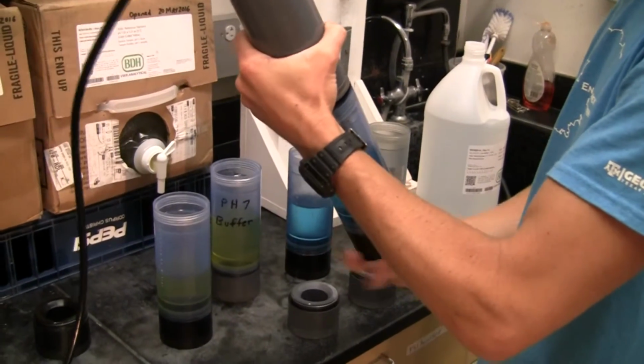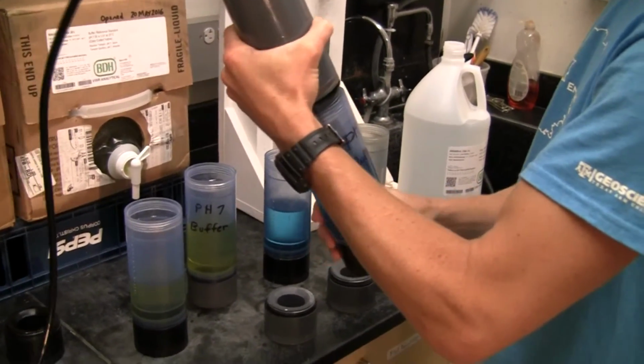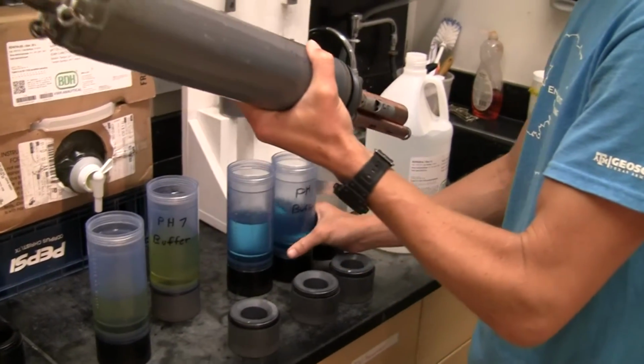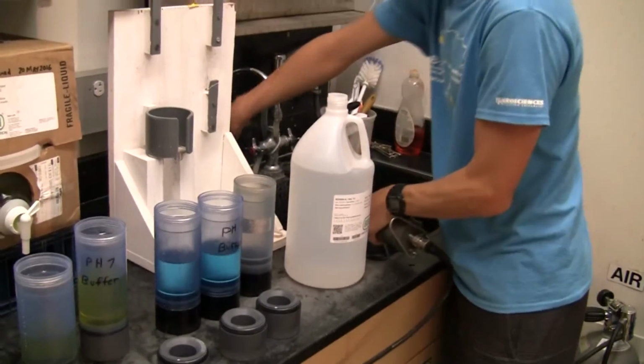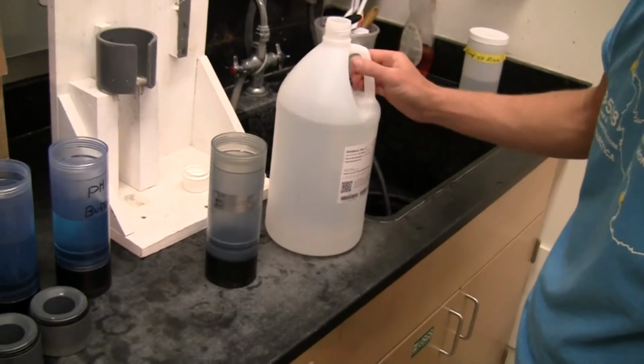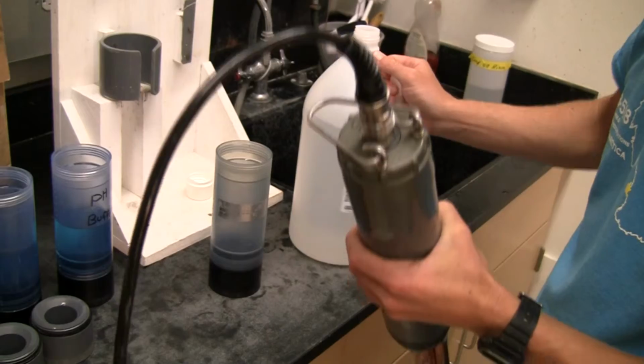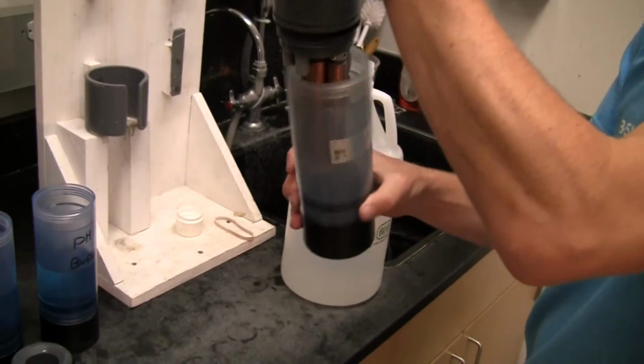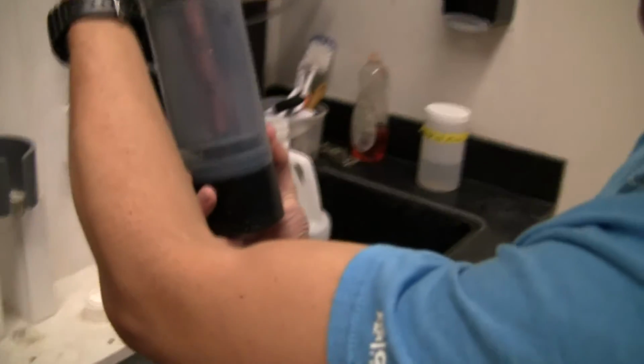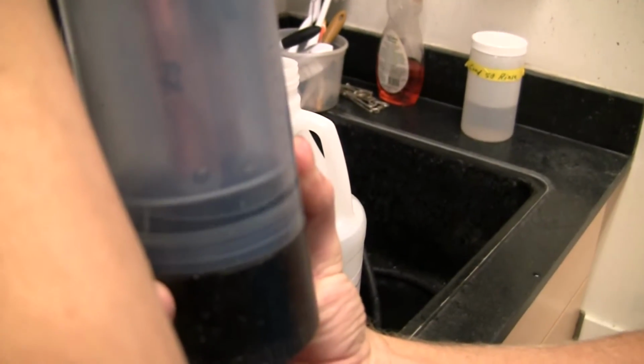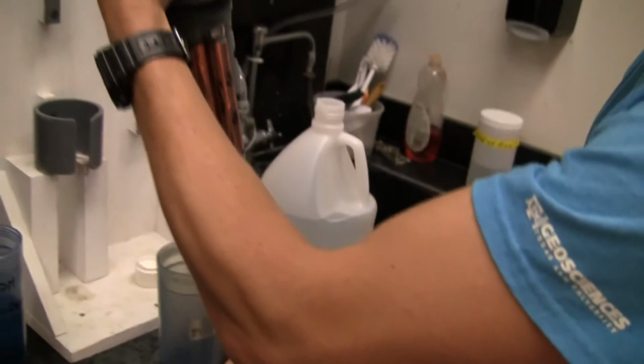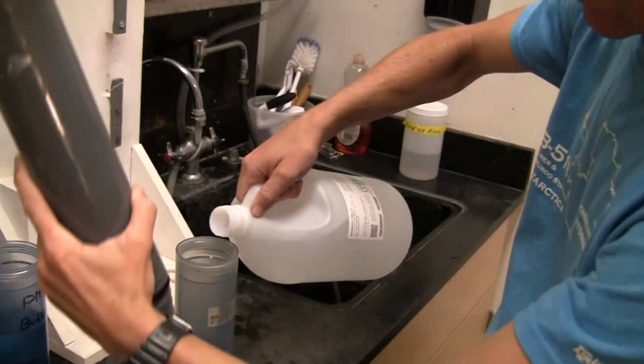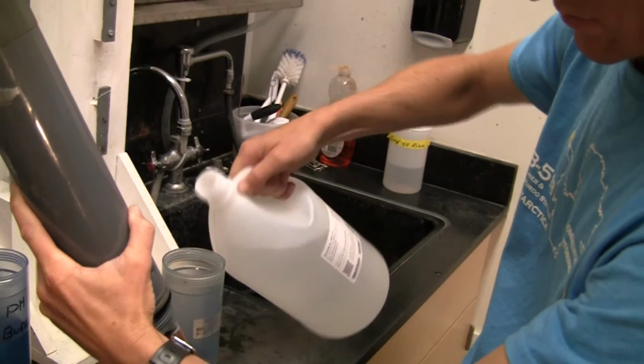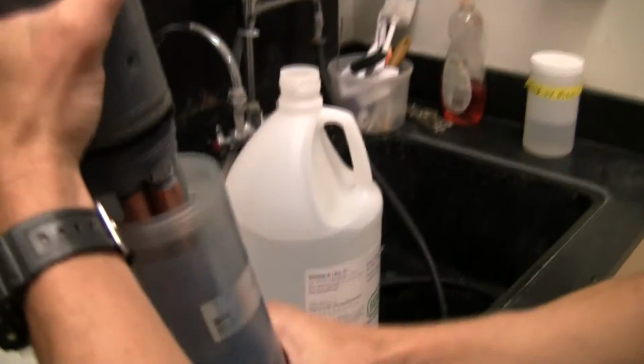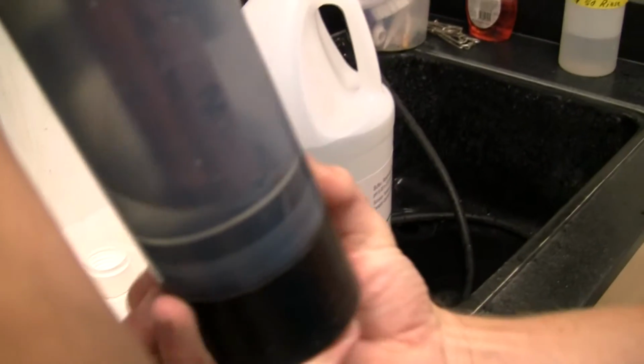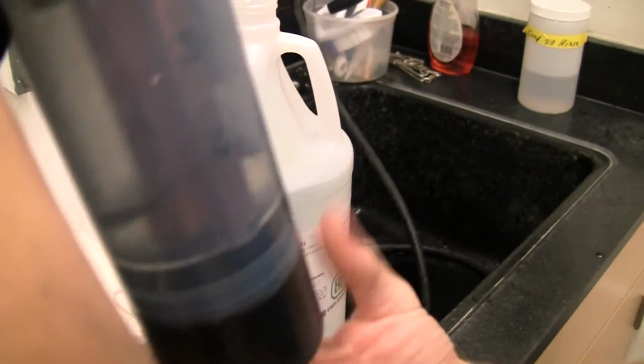Alright, so now we remove the sensor from the pH 10, and we rinse and clean with the DI water and the air, just as we did previously. So now with the sensor clean, we can place it into the calibration fluid. This is the pH check 6. Now we need to verify that the sensor itself is actually under the water, and we find that it is not in the solution, so we need to add more. Okay, looks like it's now underneath the solution.